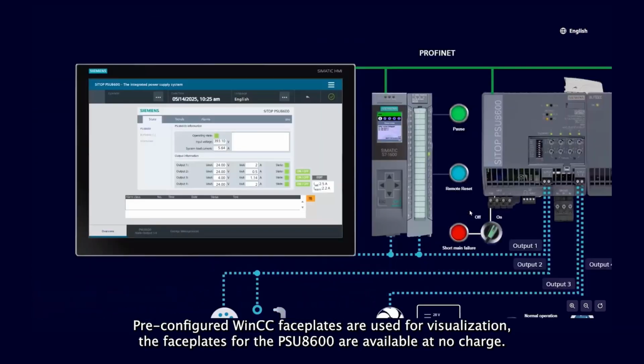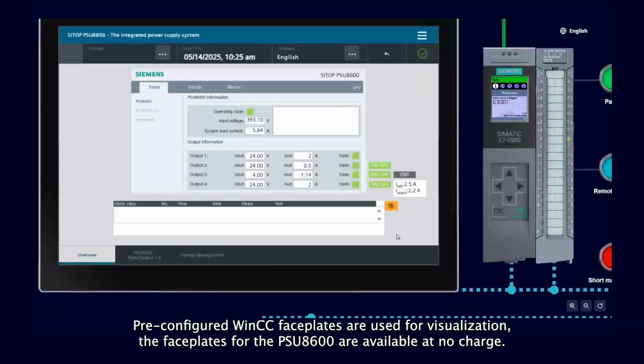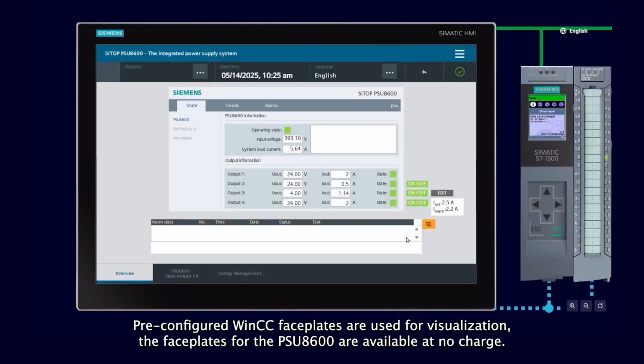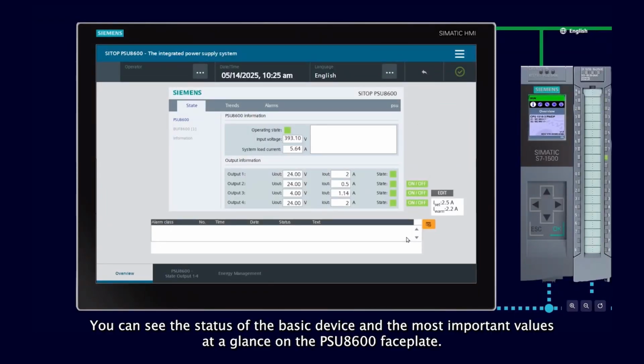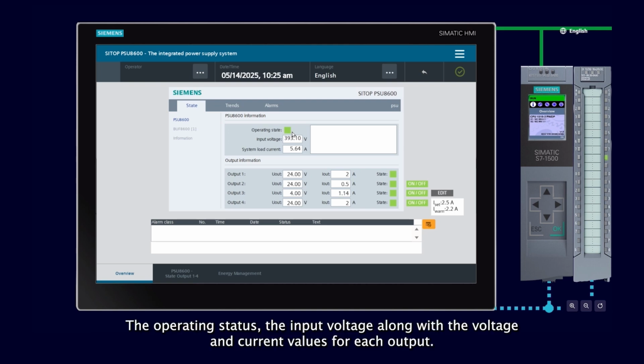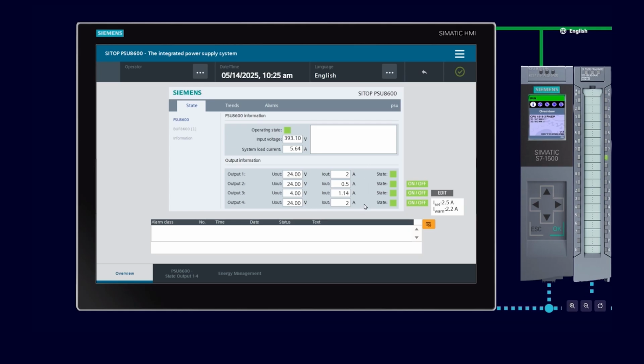Pre-configured WinCC faceplates are used for visualization. The faceplates for the PSU8600 are available at no charge. You can see the status of the basic device and the most important values at a glance on the PSU8600 faceplate: the operating status, the input voltage along with the voltage and current values for each output. The system load current is the sum of all output currents.